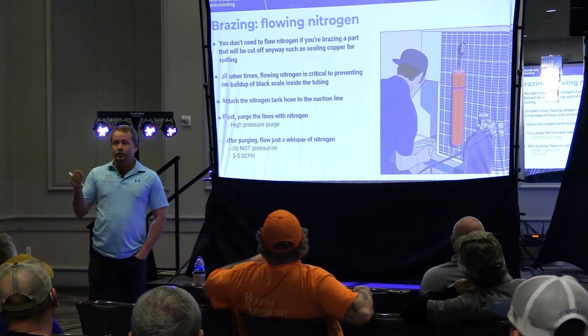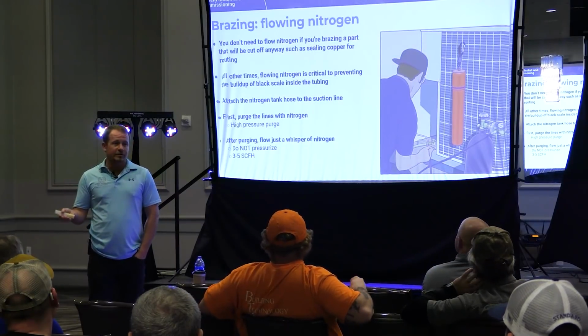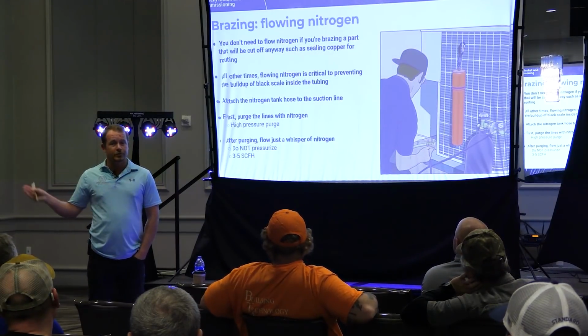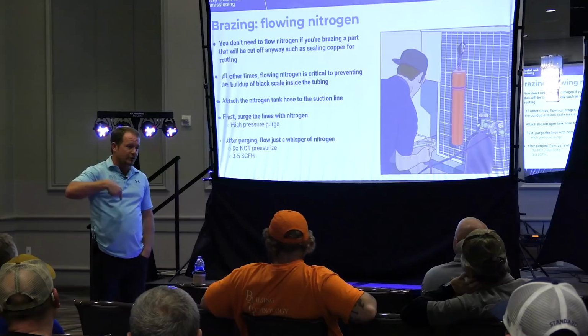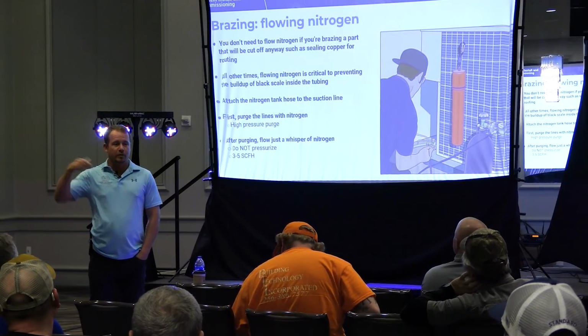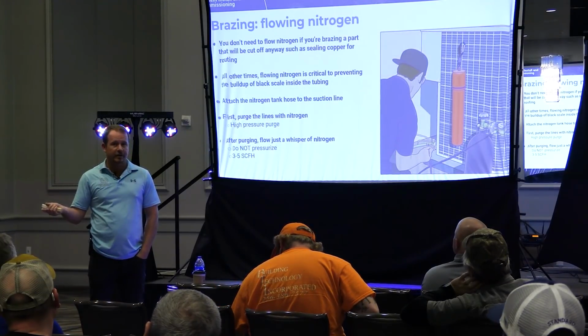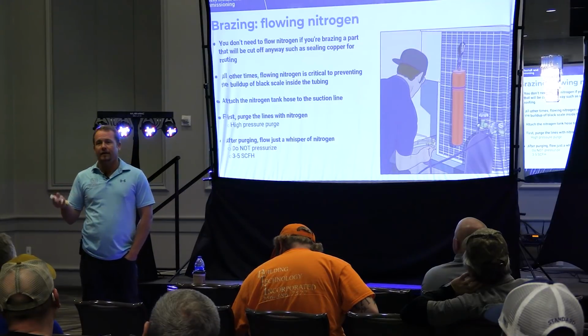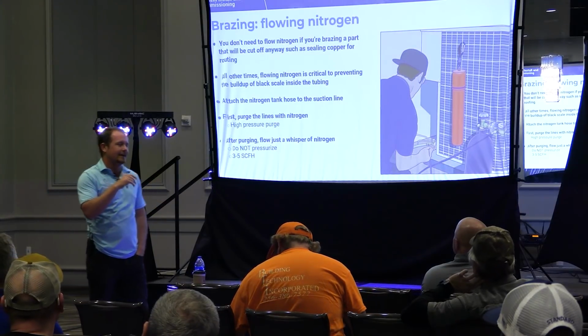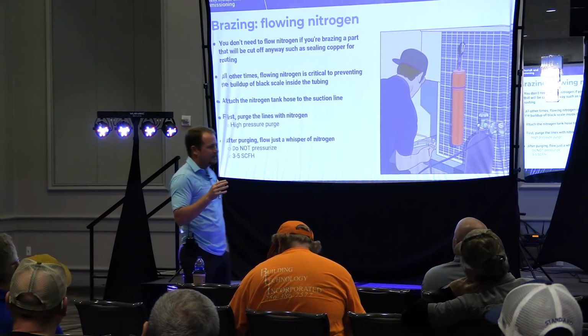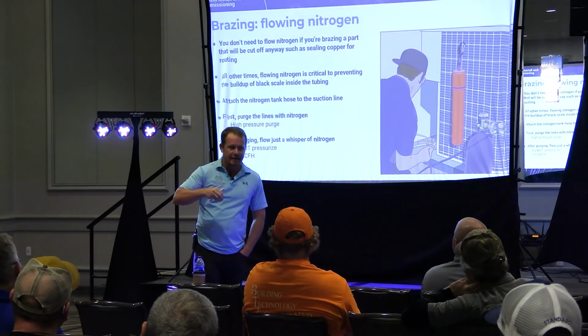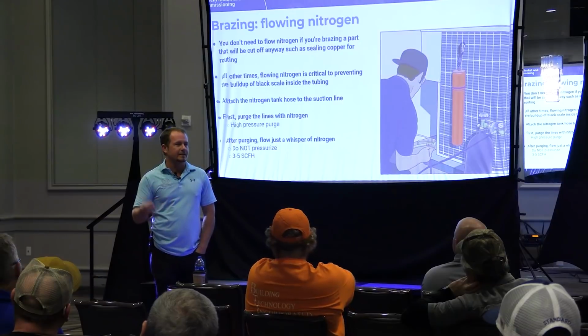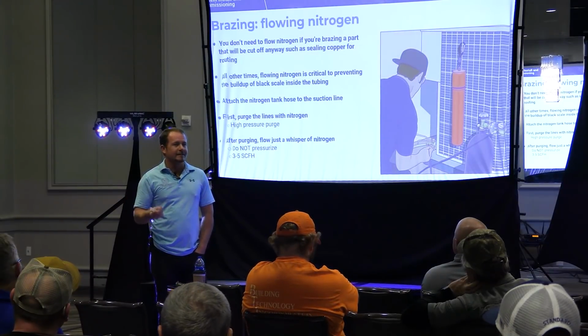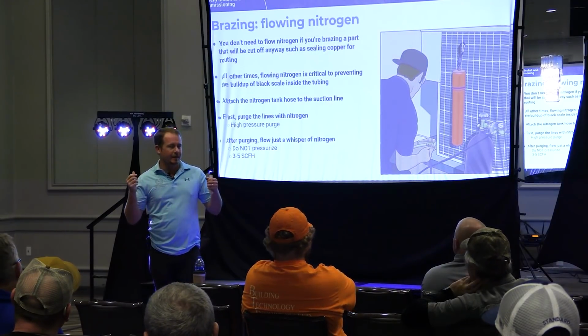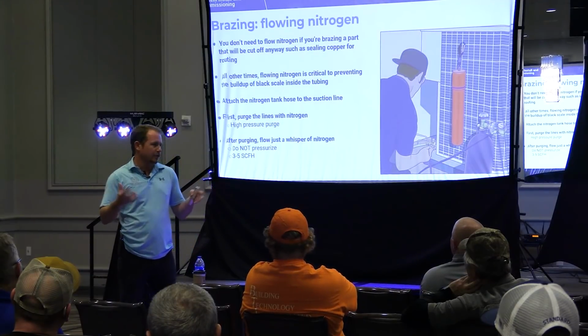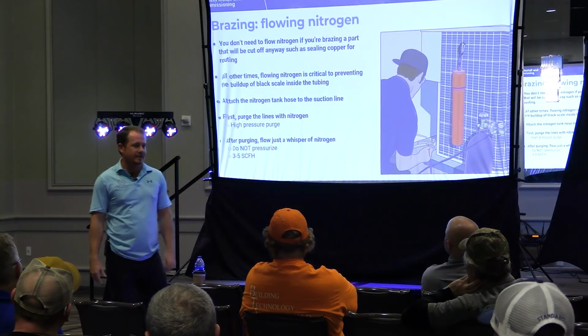But on the other hand, even if you're using StayBright 8, you should still purge with nitrogen. Even after you pressurize, purging is a really good thing, because pressurizing alone isn't the same as purging - you're still trapping some of that in there. There's the possibility, and Jim believes this happens more than it really does, that you're actually more likely to condense liquid moisture inside the system if you pressurize before purging. It's the same reason that when you compress air with an air compressor, you actually get water that drops out of that air.